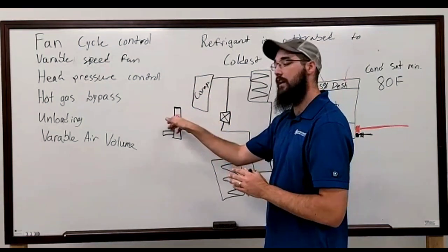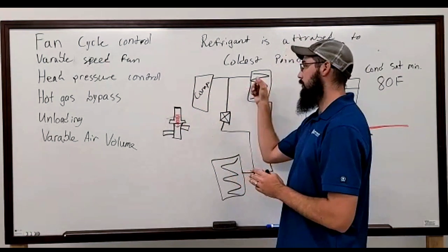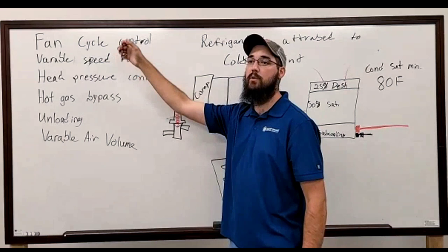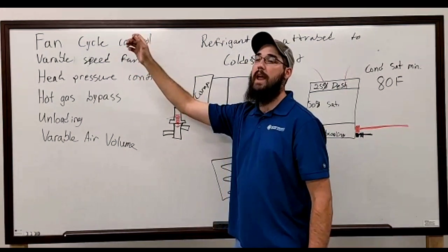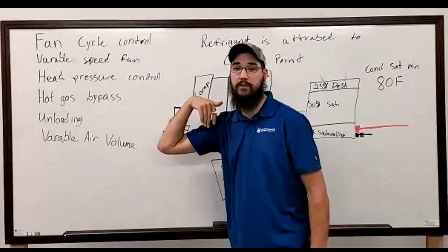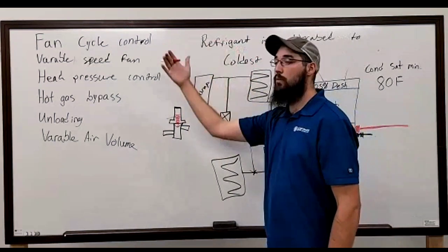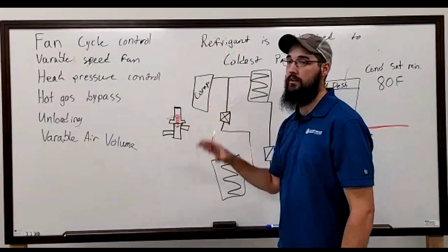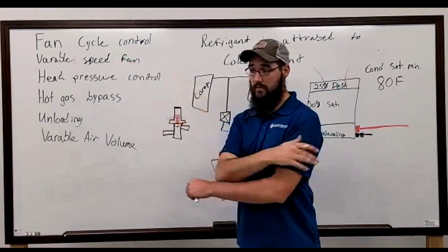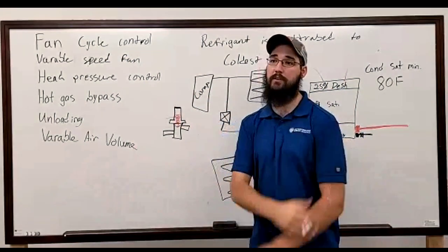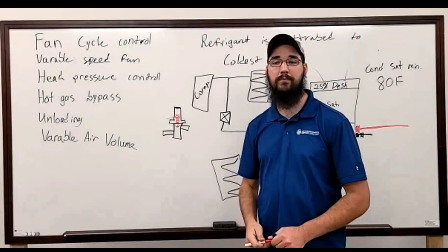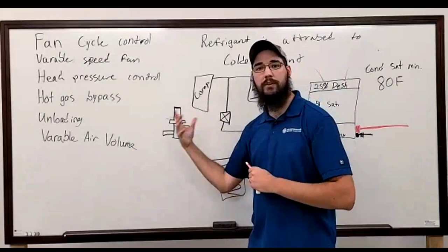Otherwise, if this is not set properly, and you can control the logic on most of these units, you can control how reactive the condenser fans are. You can make them more reactive or less reactive to head pressure fluctuations. Depending on where you set all of that will depend on how well the system will ever function. Because if you get too crazy with this, it'll just sit there and swing all day long until it breaks itself. Make sense? So you see what I mean about how these play a part together?